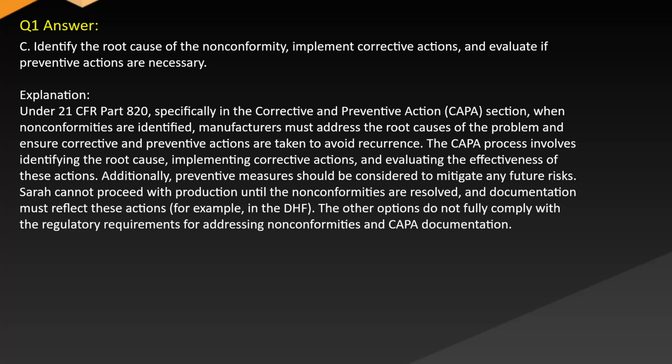The CAPA involves identifying the root cause, implementing corrective actions, and evaluating the effectiveness of these actions. Additionally, preventive measures should be considered to mitigate any future risks. Sarah cannot proceed with production until the nonconformities are resolved, and documentation must reflect these actions, for example, in the DHF. The other options do not fully comply with the regulatory requirements for addressing nonconformities and documentation.